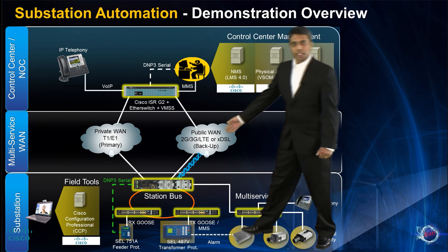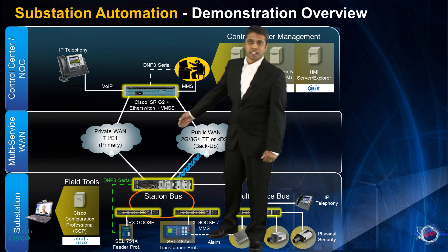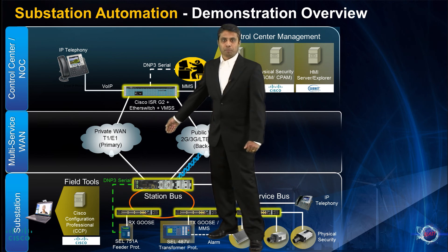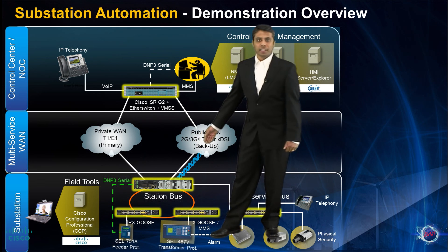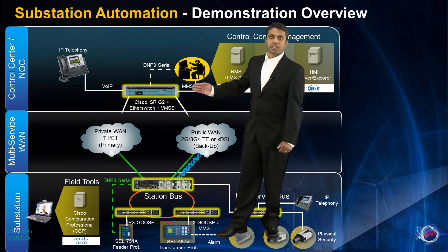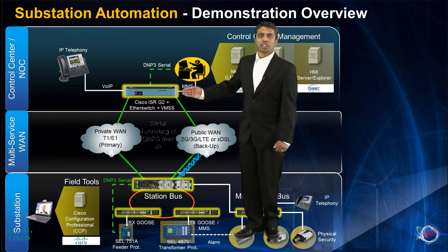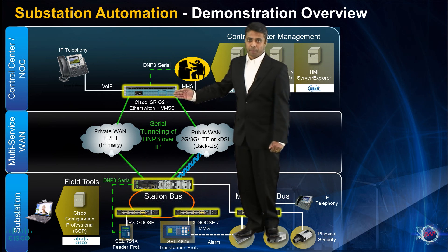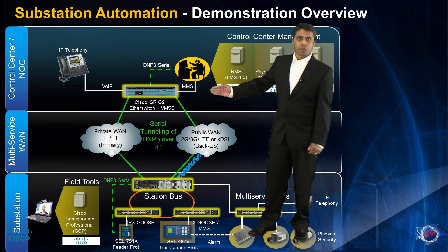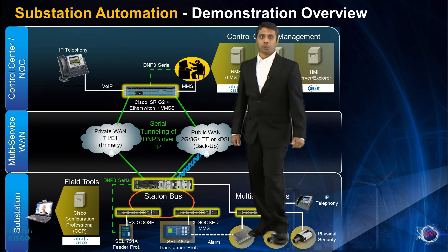Relays using legacy serial interfaces are directly connected to the router at the substation. The raw serial data is transported across the WAN to the control center aggregation router using protocols like B-STUN, or block serial tunneling. This aggregation router provides the serial connections to the HMI application, which can now talk to the relay as if it was directly connected to it.